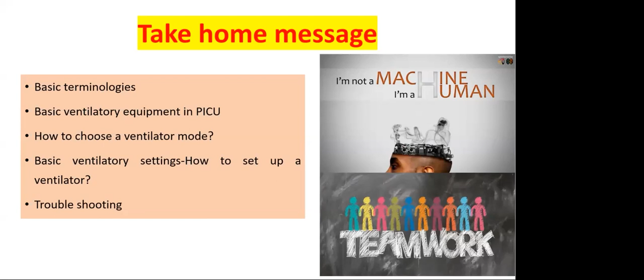What is the difference between assist control mode and SIMV pressure support mode? So assist control, as I already told, the machine will deliver whatever the set rate is. If the patient is trying to breathe in between, it will support fully. There won't be any difference between mandatory breaths and spontaneous breaths; it is almost the same.